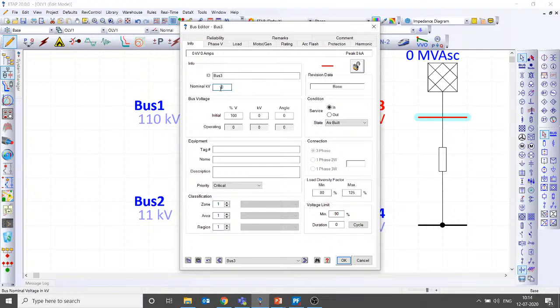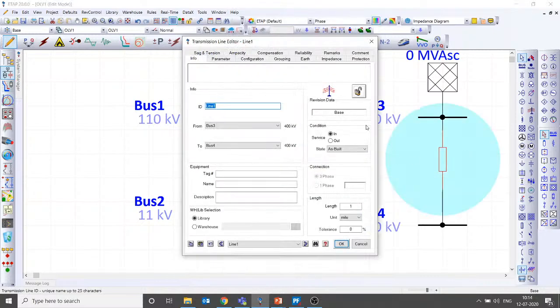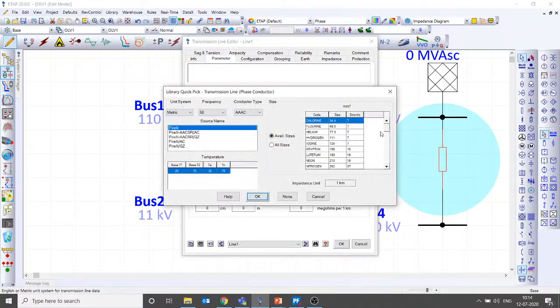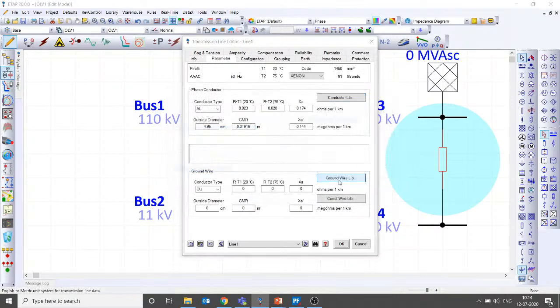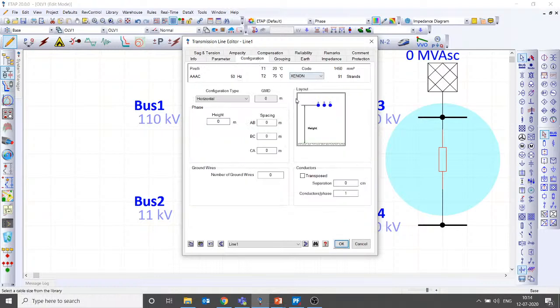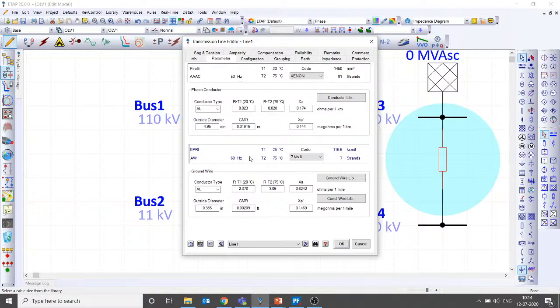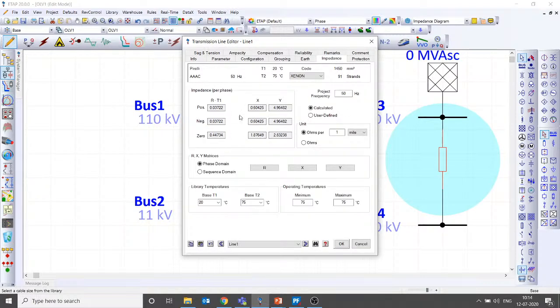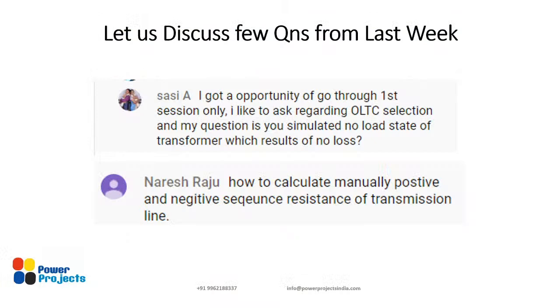If I am taking a 400 kV network, let me take two questions with respect to the simulation. The first is what he has asked: when I give these parameters, the software automatically calculates the line resistance and reactance, given the phase conductor, the ground wire, and of course the configuration of the conductors. I have assumed a horizontal conductor configuration with a single ground wire. If I give the data of height, spacing between the conductors, spacing between the phase wire and ground wire, and of course the phase conductor and earth wire details, the software automatically calculates the impedance. How to do this manually? There are quite a lot of textbooks, basic power system books, which help you answer this question. Yes, so let's move on to the next question.